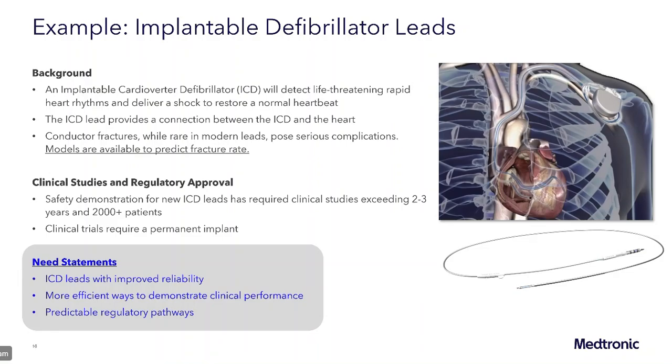And then if it's broken altogether, you might need a shock, but the device does not detect it or cannot deliver it, and then you fail to receive that shock. And obviously, that's got life-threatening consequences. So fracture of these conductor wires is a very important failure mode.